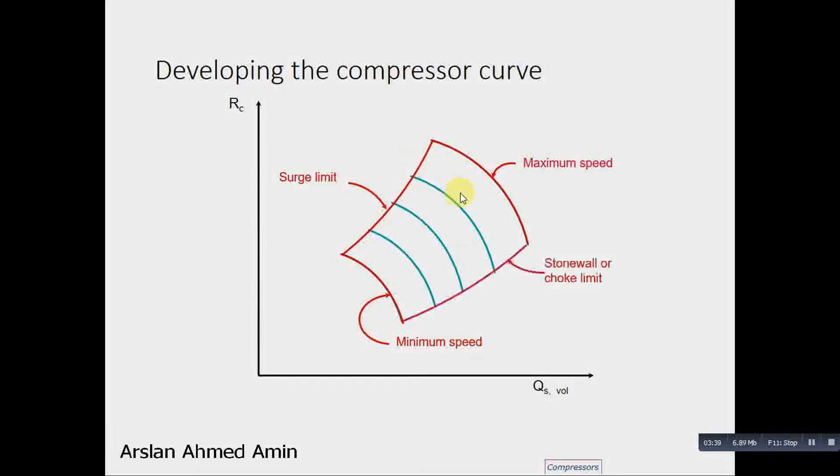And this flow is the maximum flow. This is known as stonewall or choke limit. Beyond this point, the flow does not remain stable in the compressor. And this is also a power limit imposed on the overall power of the system.